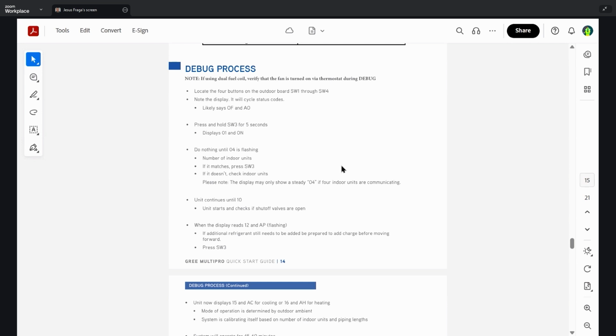Once that's verified, you're going to go ahead and go through the debug process. And as you reach each step, there's an explanation here as to what they mean. And if you get anything other than this, likely it's going to be an error code. That error code needs to be referenced back to the service manual to see exactly what that is, or on the back of the service panel, which will tell you what that error code means.